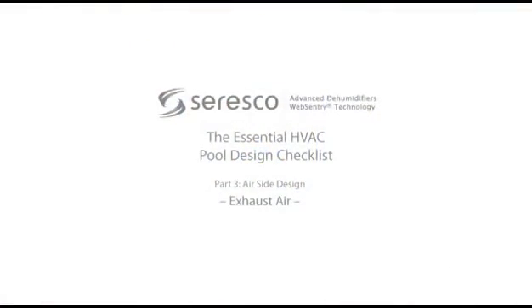So once you've established your 0.48 CFM per square foot of wet deck and pool baseline outside air requirement, if you happen to have a spectator area, in addition to that baseline calculation, during a swim meet, you need to include 7.5 CFM per spectator on top of the baseline. If you don't have a spectator seating gallery, your baseline calculation is definitely adequate.